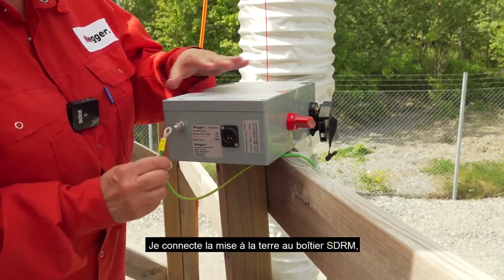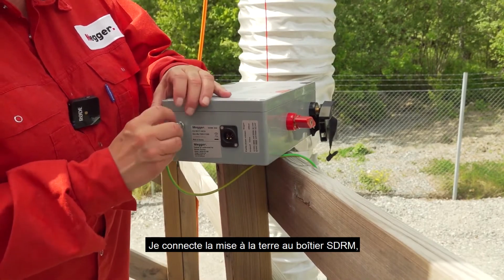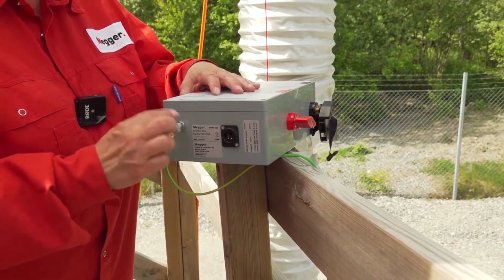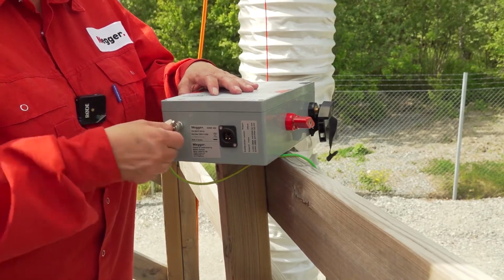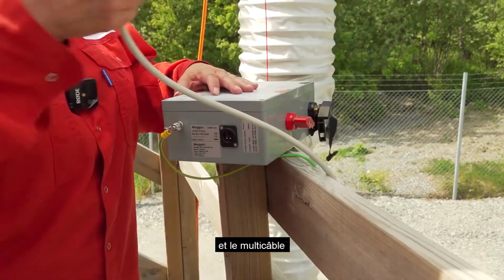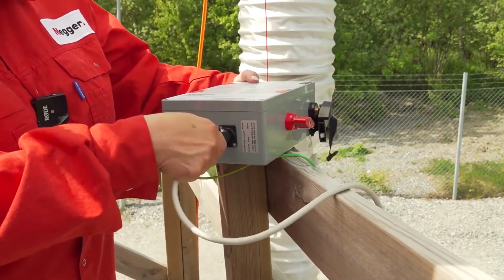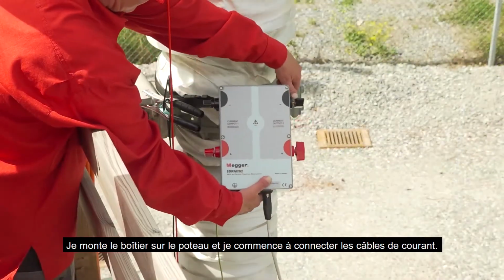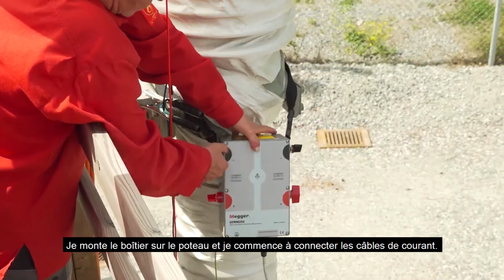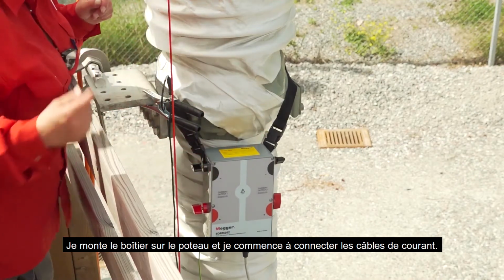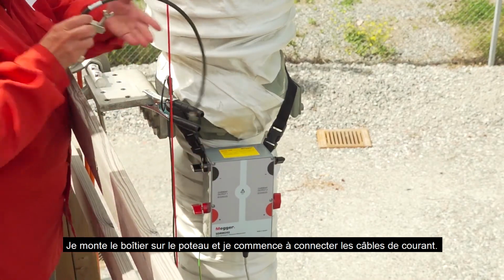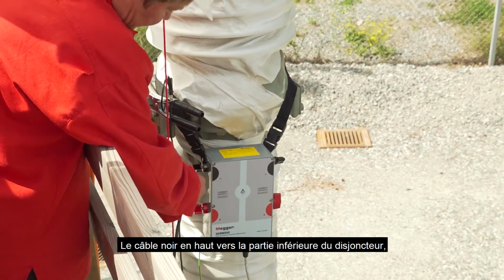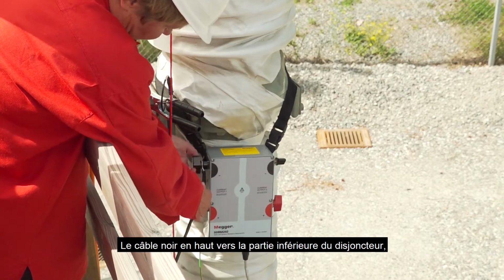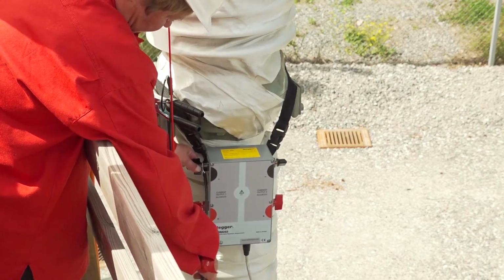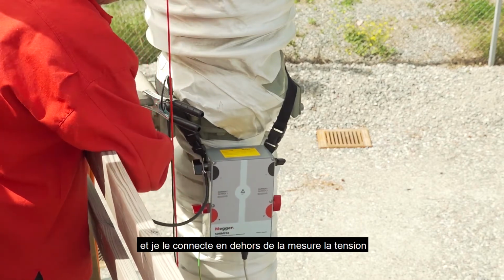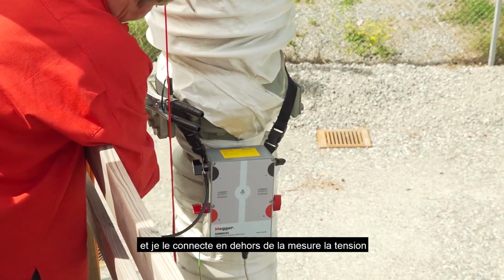I connect the grounding at the SDRM box, and the multi-cable. I mount the box at the pole and I start to connect the current cables. The black cable at the top to the lower part of the circuit breaker, and I connect it outside the voltage sense.